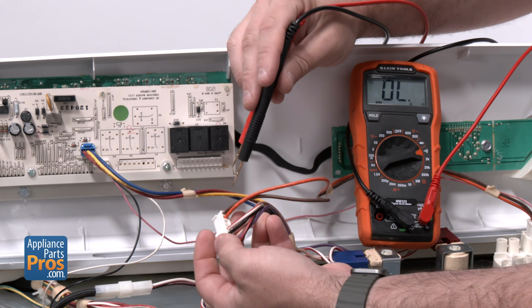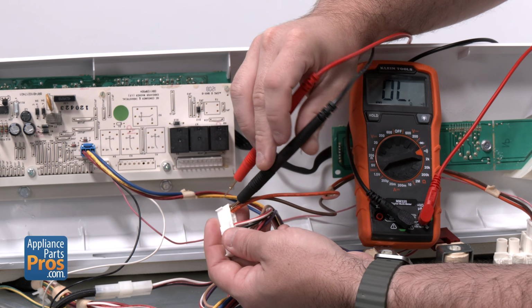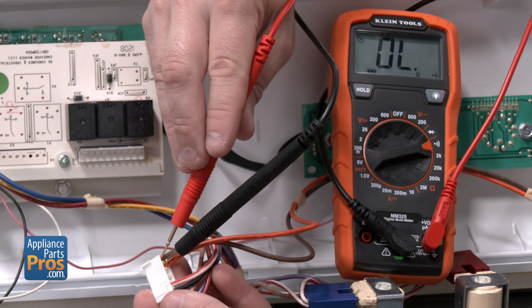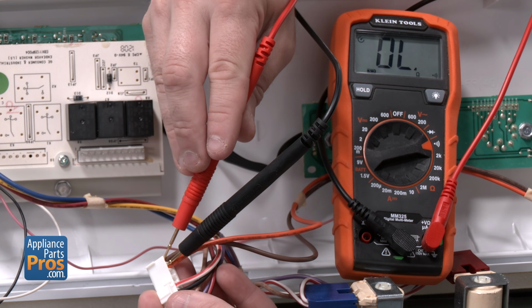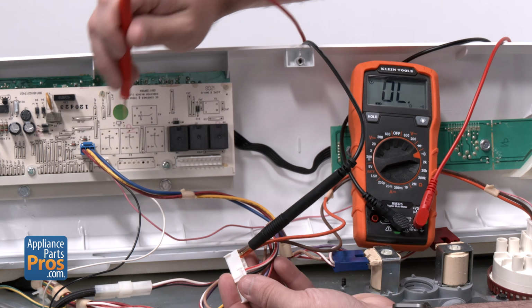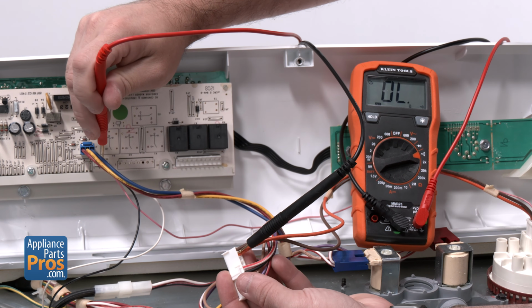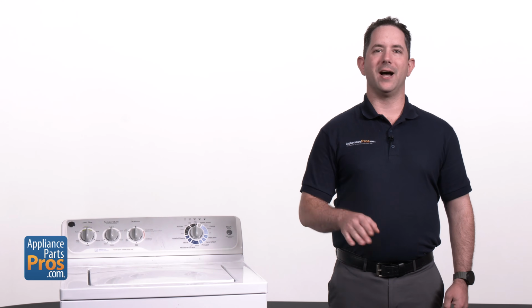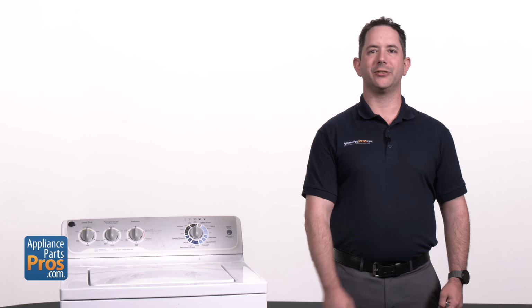We're inserting the black meter probe into the orange wire and leaving it there; it is our common wire. We're inserting the red probe into the brown wire to test for continuity. We're moving the red probe over to the pink wire at the 5-pin connector of the main control and testing for continuity. If either test shows continuity, the pressure sensor has failed.